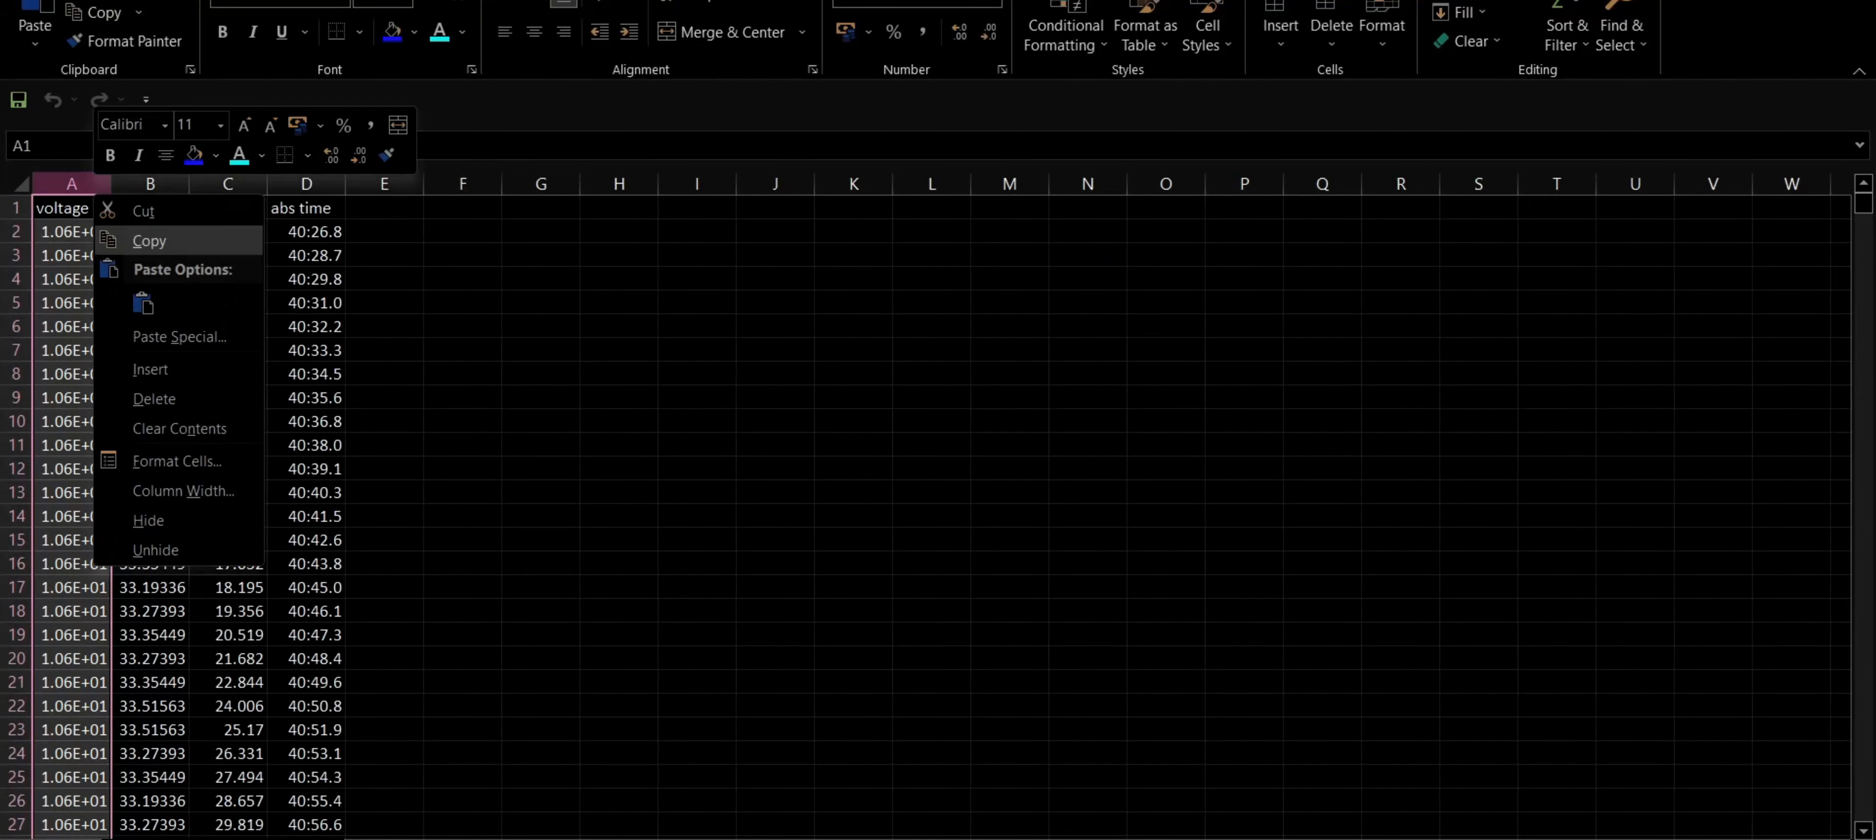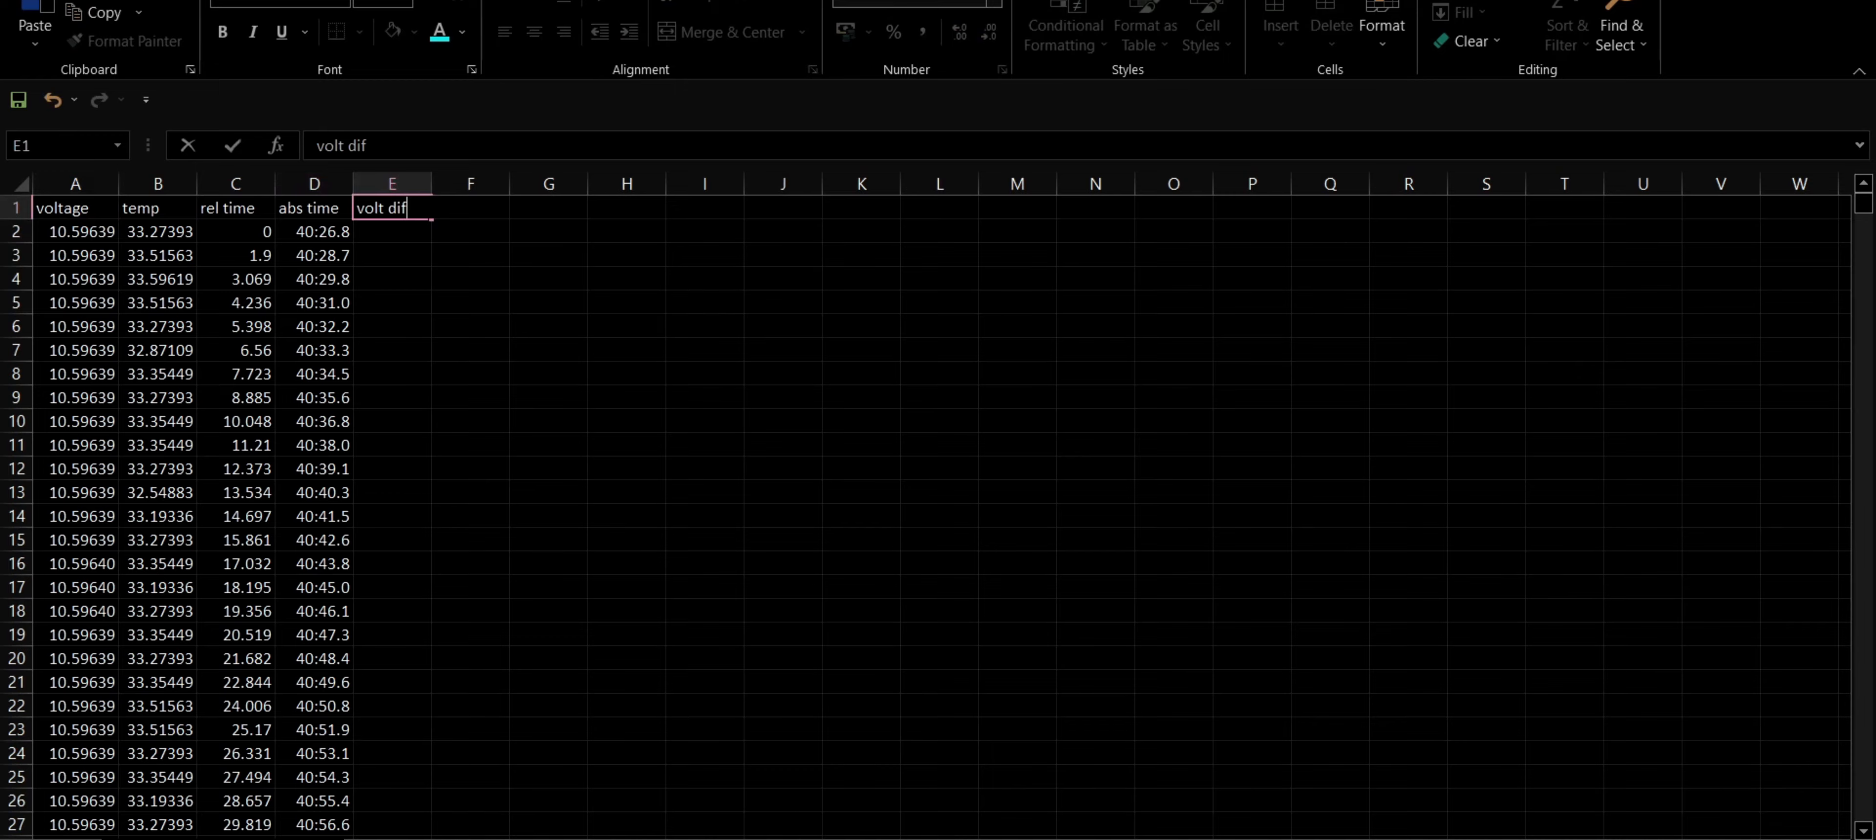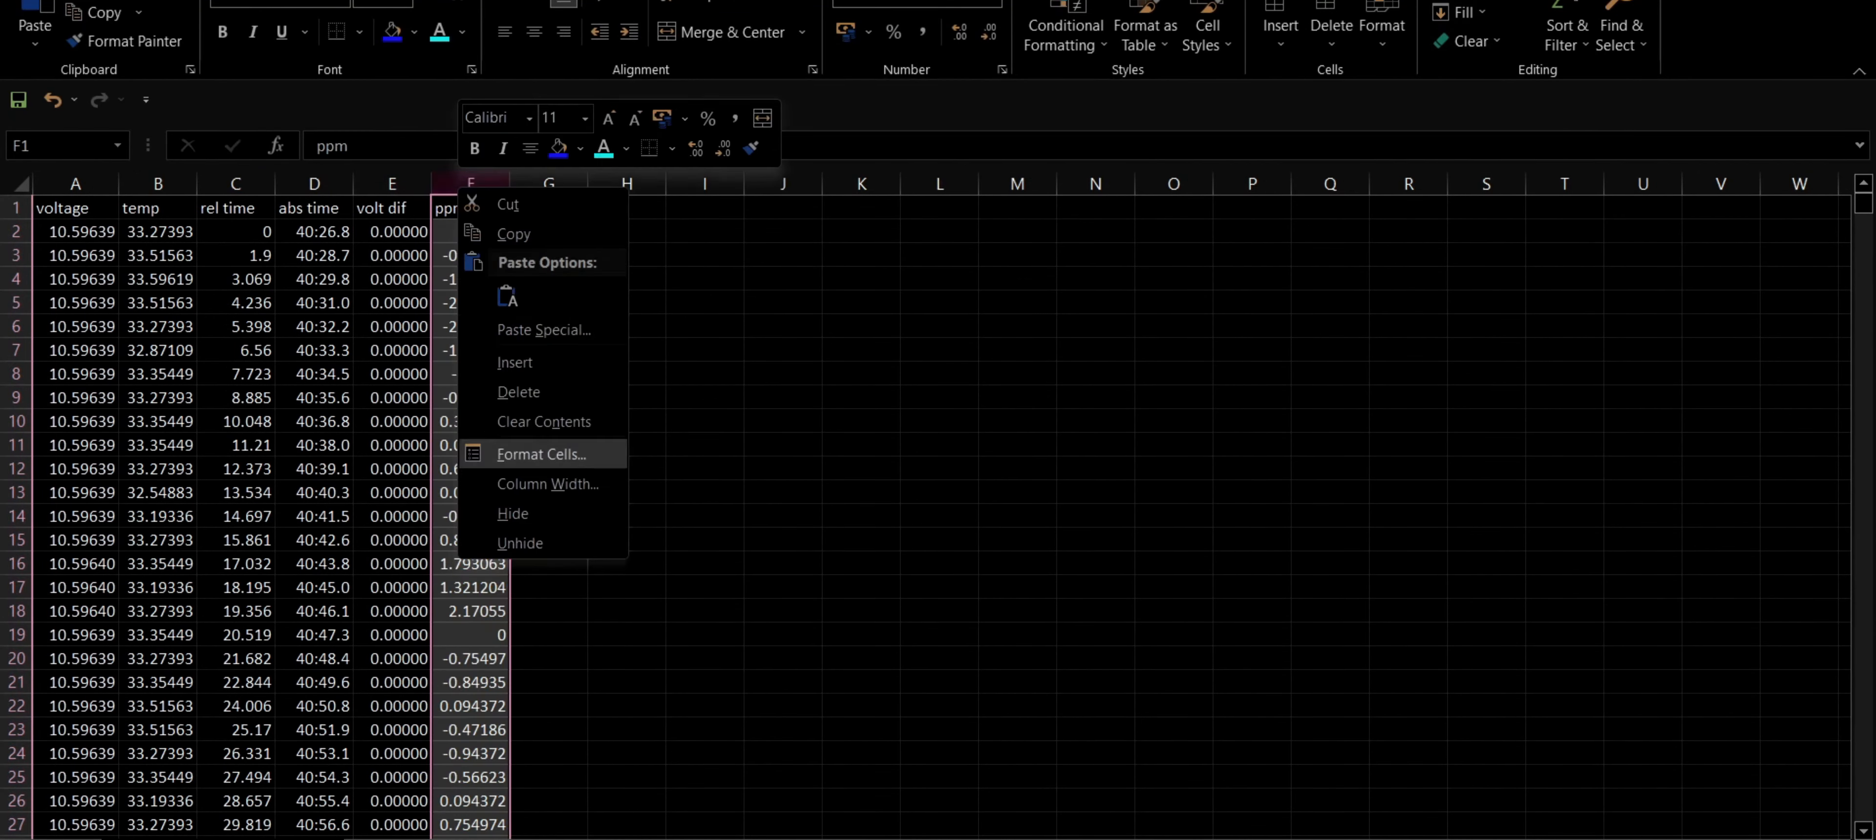First off, I will set the number of decimal places on this voltage column to 5 so I can see exactly what is going on. Then I will copy the first voltage and subtract it from itself. This first voltage is now our zero PPM reference. This column records the voltage difference of each successive reading from the initial reading and by dividing this difference by a millionth of the initial voltage, we finally get the PPM values.